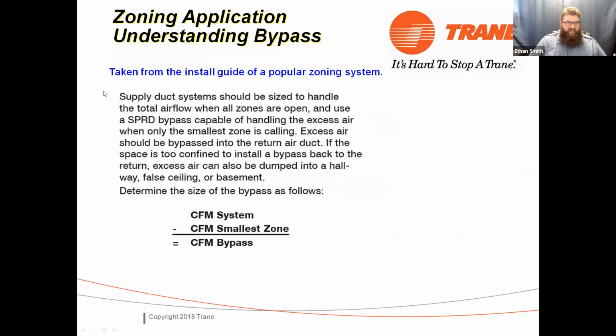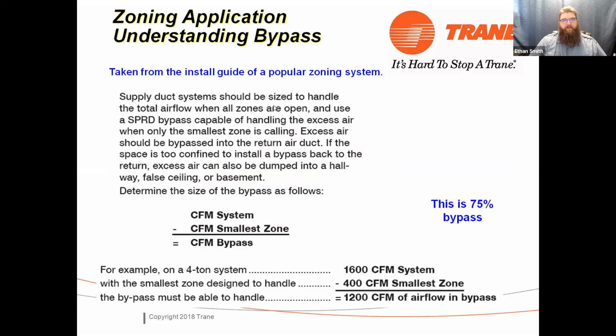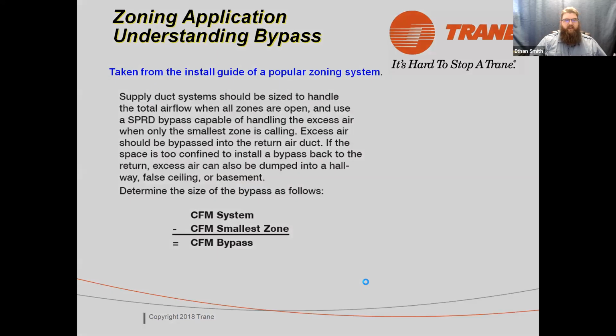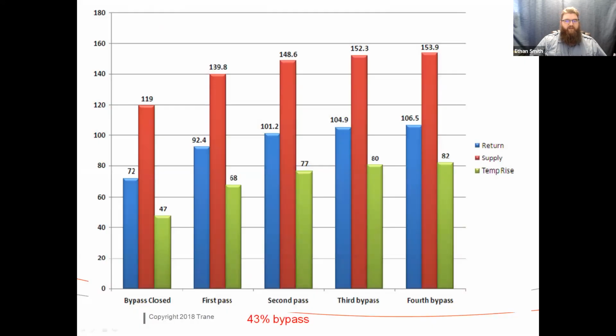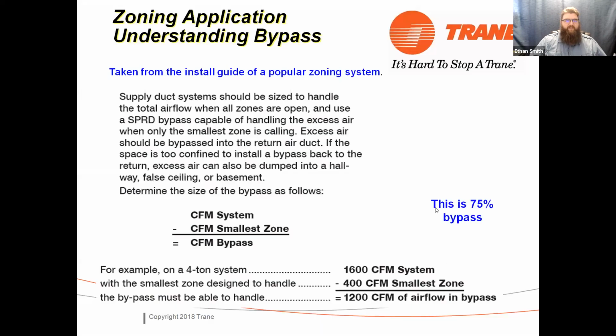So this is taken straight from a zoning manual, guys. They talk about that. This is their example on a 4-ton system at 1600 CFM. The smallest zone that it's designed to handle is a 400 CFM zone. So that's a 25% zone. So they tell you that your bypass must be able to handle 1200 CFM. Okay. I'm doing this to my furnace with a 43% bypass. What am I going to do with a 75% bypass? This is out of a zoning manual, guys.